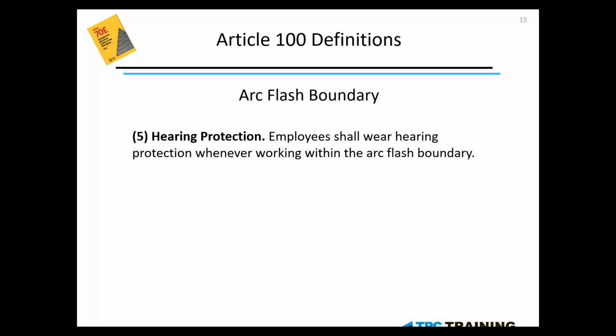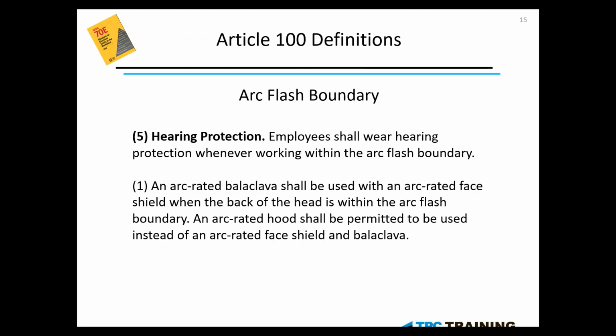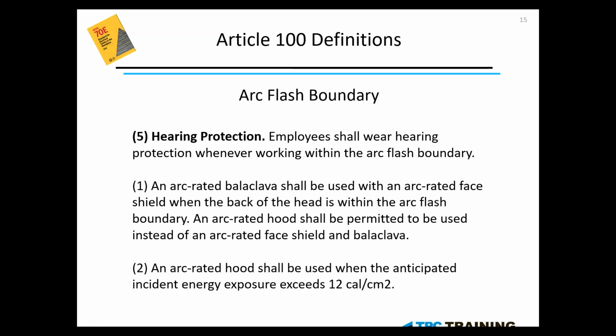These are some requirements that have been introduced recently. One is that while inside that arc flash boundary, employees shall wear hearing protection whenever working inside that boundary. Also, while inside that boundary, they shall wear an arc-rated balaclava to protect the back of the head. Now, this is in conjunction with a face shield. If a person or an individual group decides to go with the hood instead of the shield, then that balaclava would not be required. An arc-rated hood shall be used when the anticipated incident energy exceeds 12 calories. And also if you choose to do so inside of the arc flash boundary, underneath or below 12 calories, you could certainly do so. But just pointing out that a balaclava is required within the arc flash boundary.